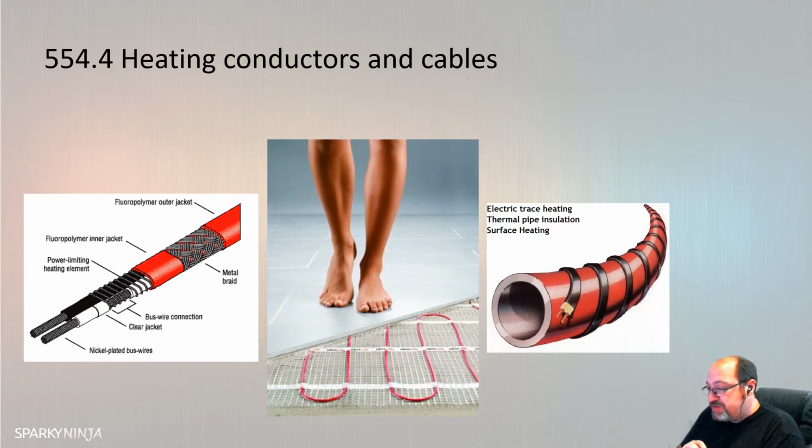during installation and use. A heating cable intended for laying directly in the soil, concrete, cement, screed, or other material used for road and building construction must be capable of withstanding mechanical damage under conditions that can reasonably be expected to prevail during its installation. It's during installation that this kind of thing is most vulnerable, because obviously once it's laid and it's done properly, it's fine. But whilst it's being installed, there's obviously lots more external factors and risks of impact and damage to it. It will be constructed of material that will be resistant to damage from dampness and corrosion under normal conditions.